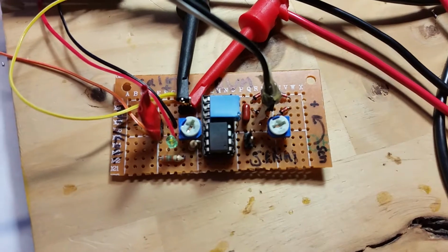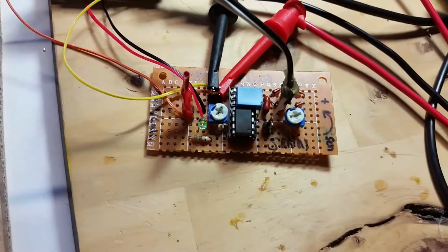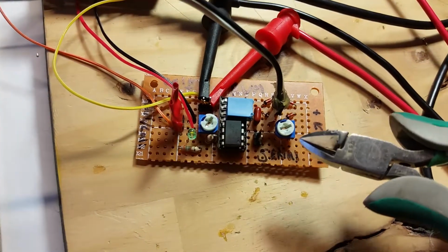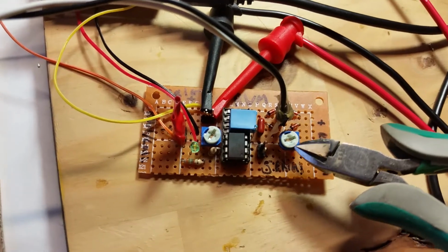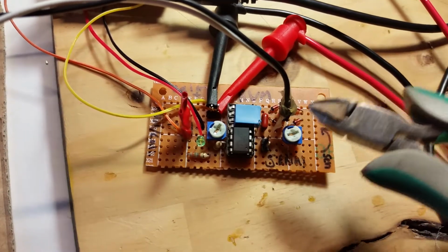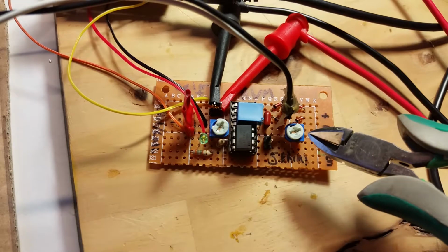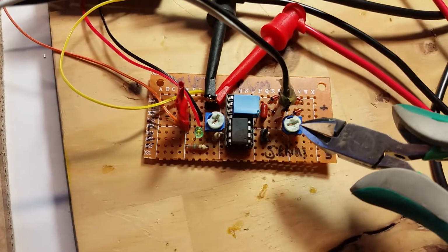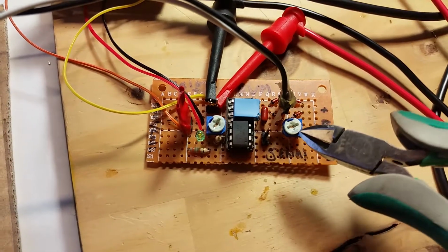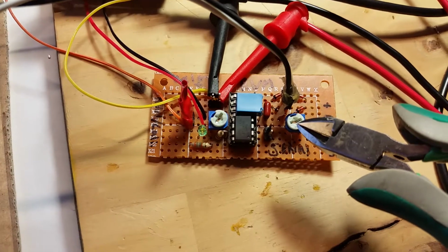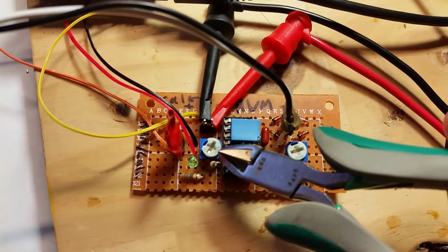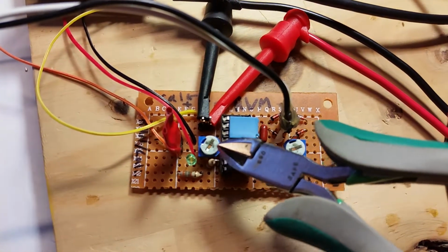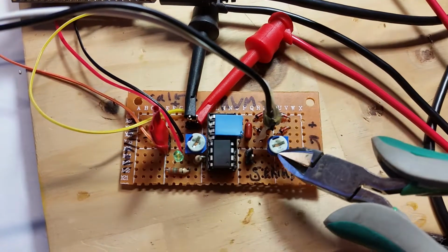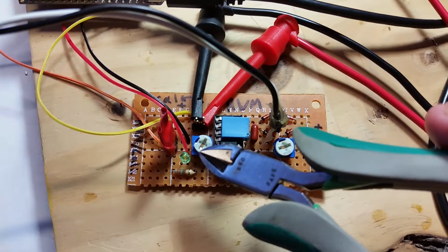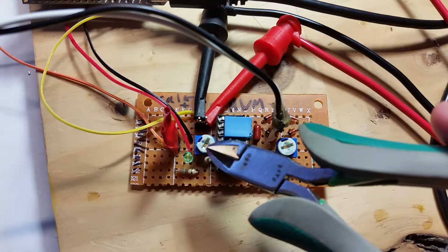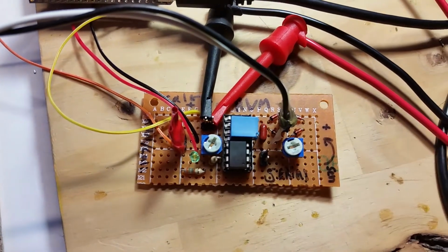this has two potentiometers. There's one on this side, and this is a sensitivity. If the voltage of the power coming in is too high, you can dial this down. I don't think that we'll need to use this, but in some applications you do. And this is kind of just the calibration, so we can do a fine control. So you want this basically as sensitive as possible, and then you want to dial this in to be in the right range.